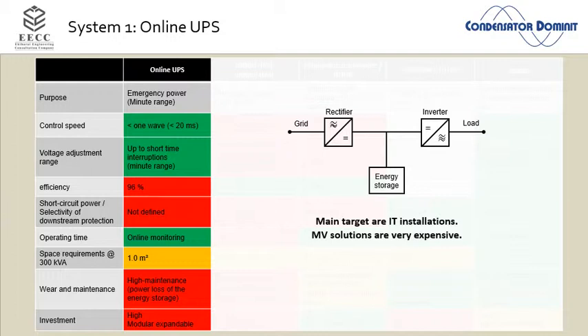Okay? If I reduce my short circuit power, it means my grid impedance goes drastically up. But that means my harmonic distortion is just ramping up. We had a case with a German pharmaceutical factory. It was a wonderful thing.